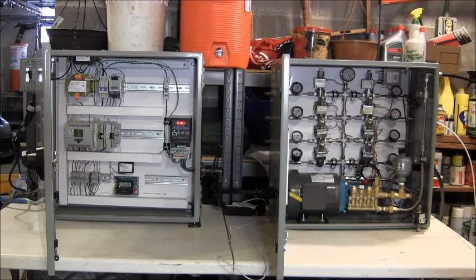Now this device down here, these two small devices, this is actually a timer. It's a 7x24 timer, or 24/7 timer, where you can cycle this unit on and off through that timer. That timer is right into the start-stop circuitry, and if you wanted to set it to quit at midnight and start back up at 6 a.m., you can use that timer right there. You can also use this microcontroller to do that, but then you need to have an interface, which I'll demonstrate after a while.